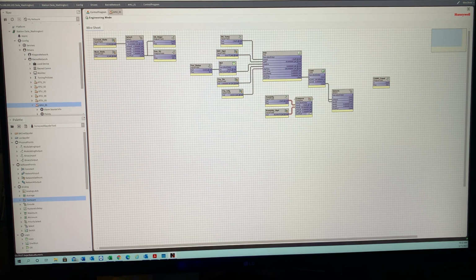Let's say your humidity is fluctuating a lot -- this applies just to humidity, but you could do it on everything. Say you want to make sure that once it hits 60%, your humidity control comes in, but you don't want it to turn off until it gets down to about 4 to 5% lower. You can set the off value to 5, so the compare block isn't just bouncing on and off. It just depends on what you're trying to do.